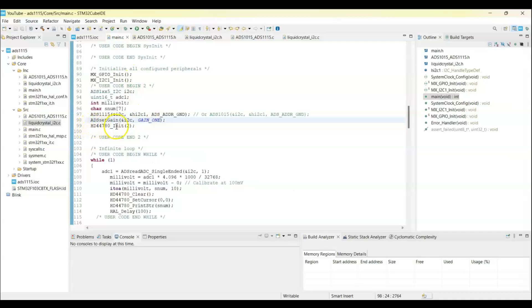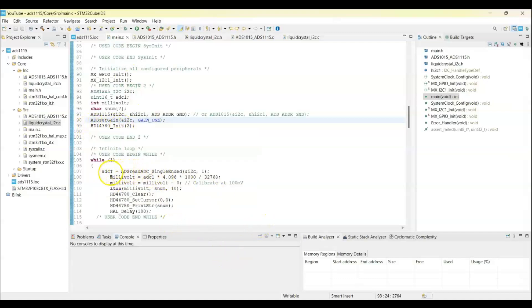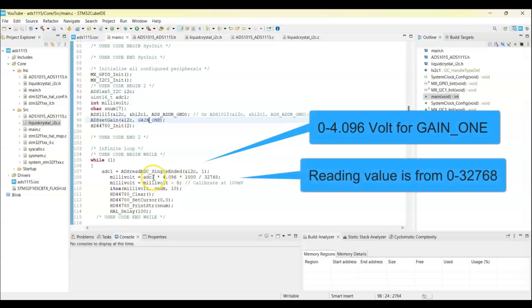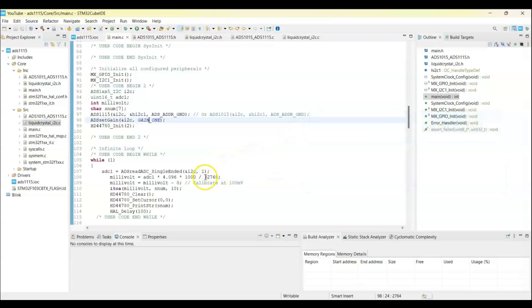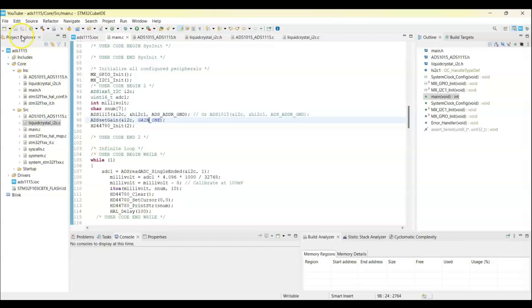In the while loop, we get that single-ended value from the 1 position where there are 4 inputs - we use input 1. This is how we convert into millivolt, because this one goes from 0 to 32768, so that's why we divide by 32768. And this is the maximum volt, 4.096 volt, so multiply by 1000 to get millivolt. This one is to correct the error, to calibrate if there is doesn't go to 0 - we subtract or add that value. I'll show you later. We convert into string and then put into the display.